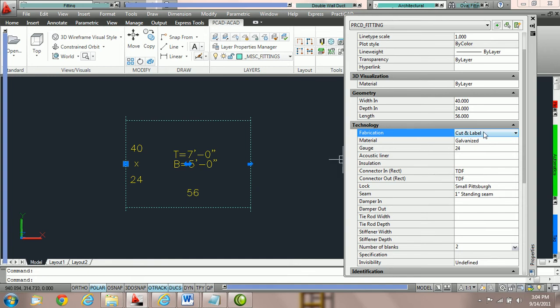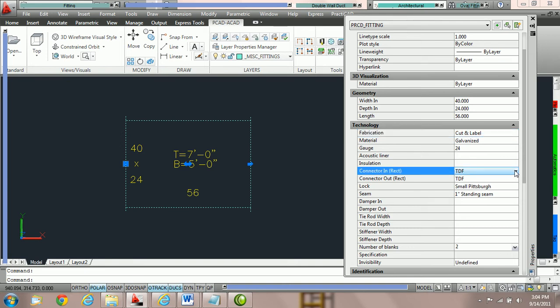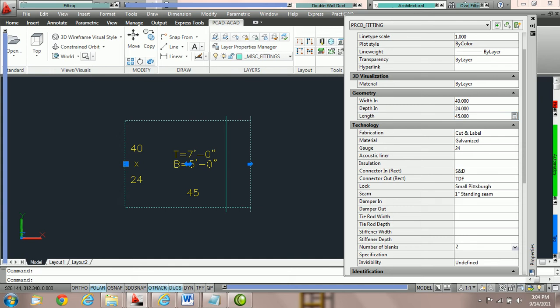We've switched the fabrication level to cut and label and now we're going to change the connection to slip and drive. Notice when we switch it to slip and drive, it does not affect anything else — it doesn't affect the length in particular. If we decide to switch the length to 45, it will automatically adjust the fitting to fit exactly what we've typed in. Cut and label means we're going to fabricate this fitting, send it to the plasma, and it shouldn't follow any rules in terms of default stock length.